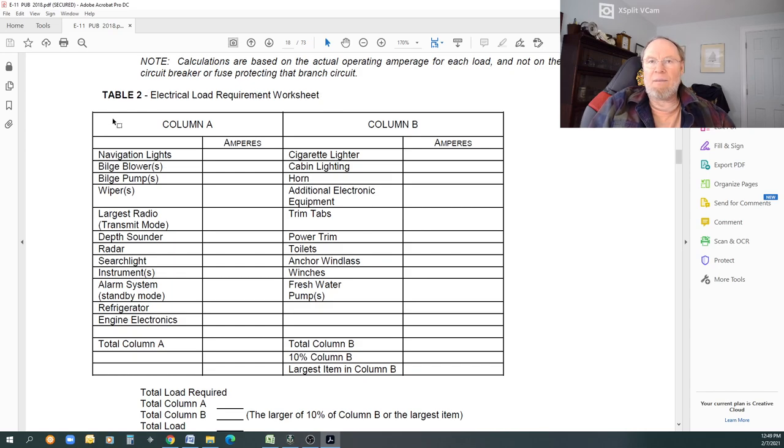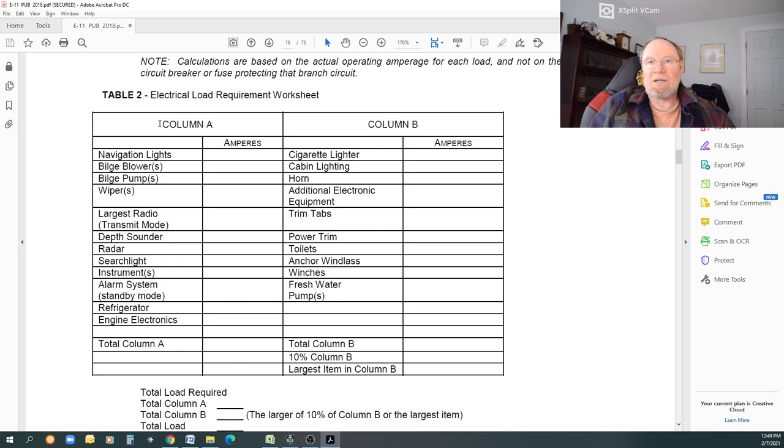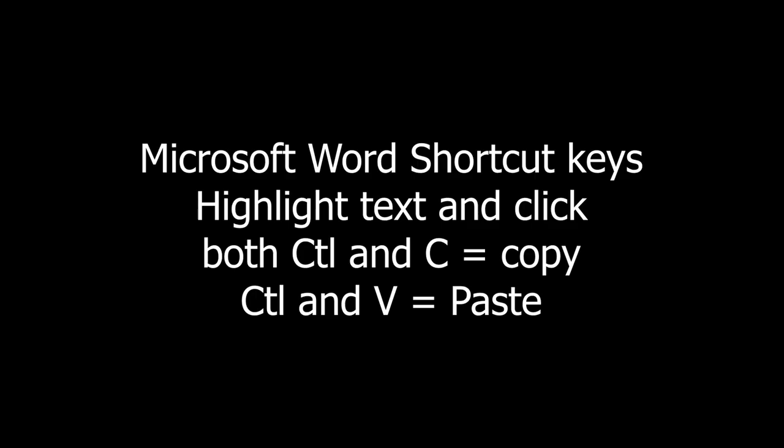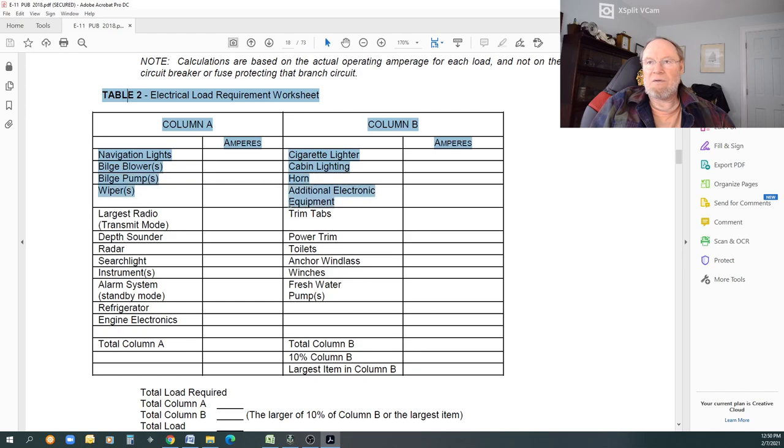The biggest thing to understand is what we're looking for is we're trying to figure out what the maximum current flow through this DC panel is going to be so we can figure out what that actual fuse size and wire size is. So let's get started. So I want to copy this and put this into Excel to make it a little easier for me to comprehend. Now, two ways to do that. One is you try to drop it into Excel and it doesn't work. So we're going to use Word first.